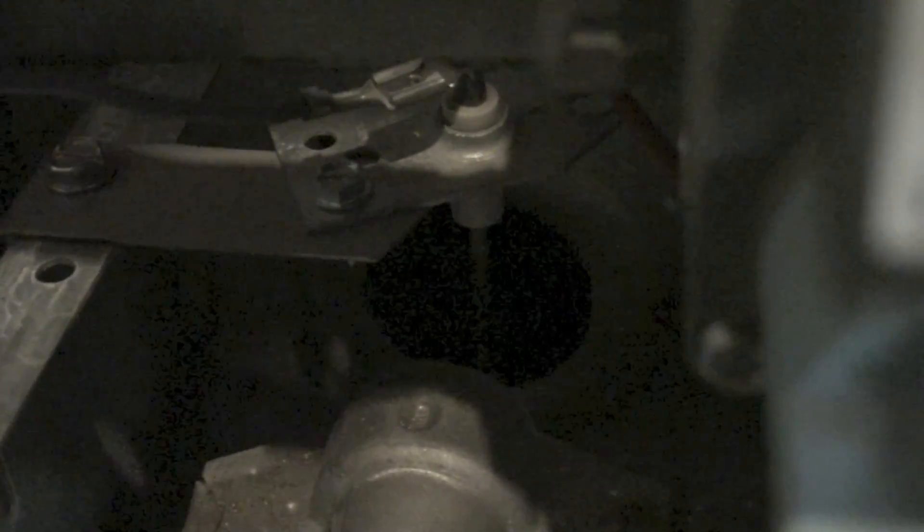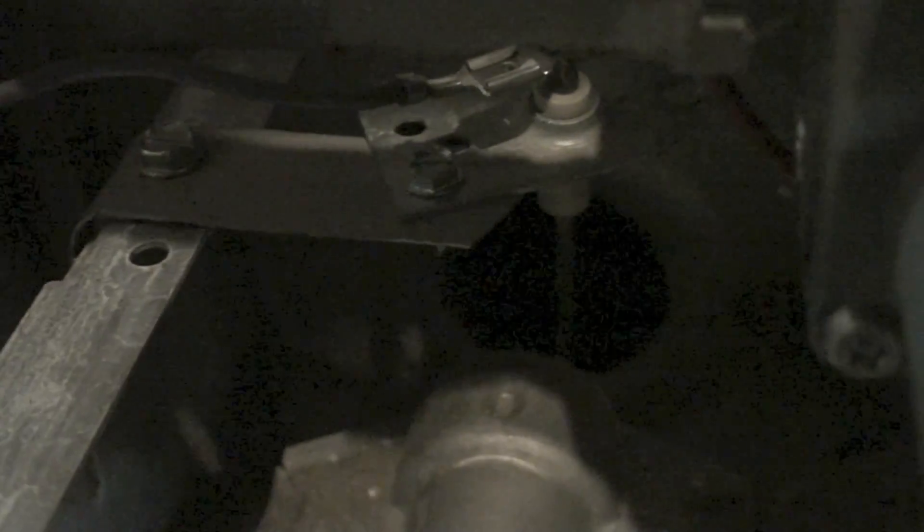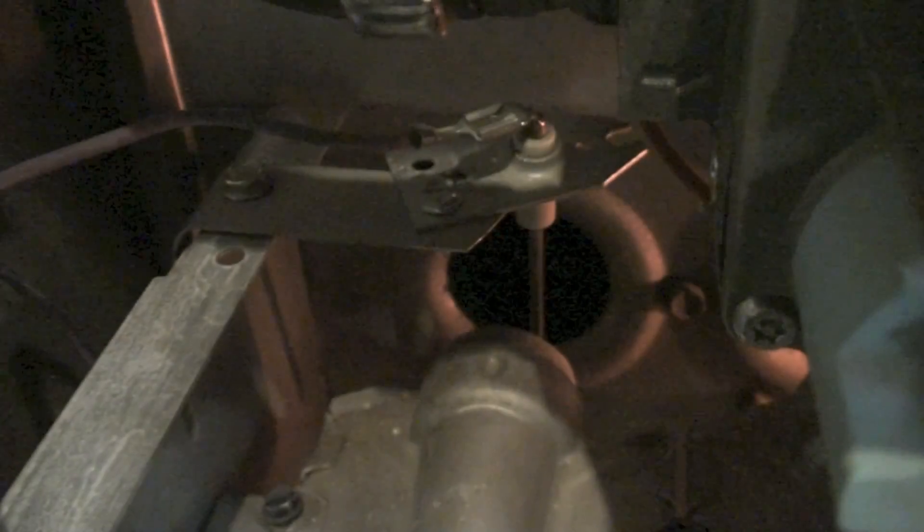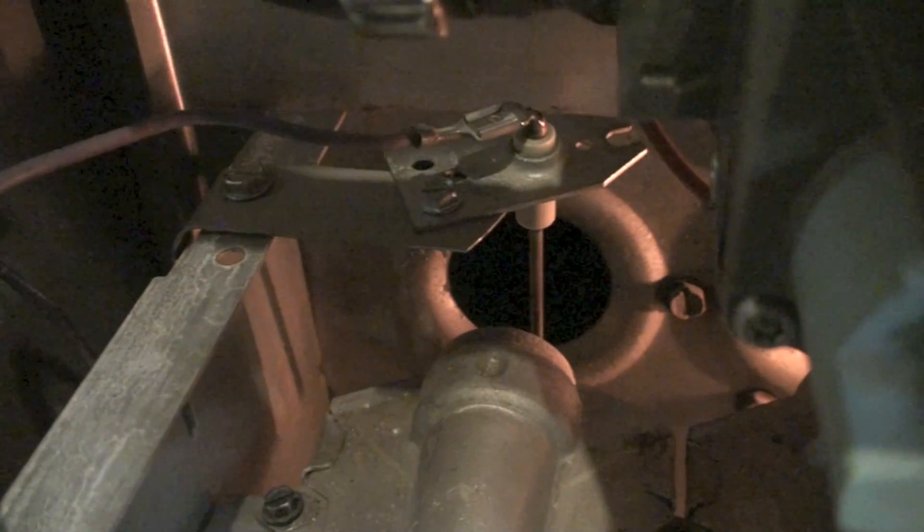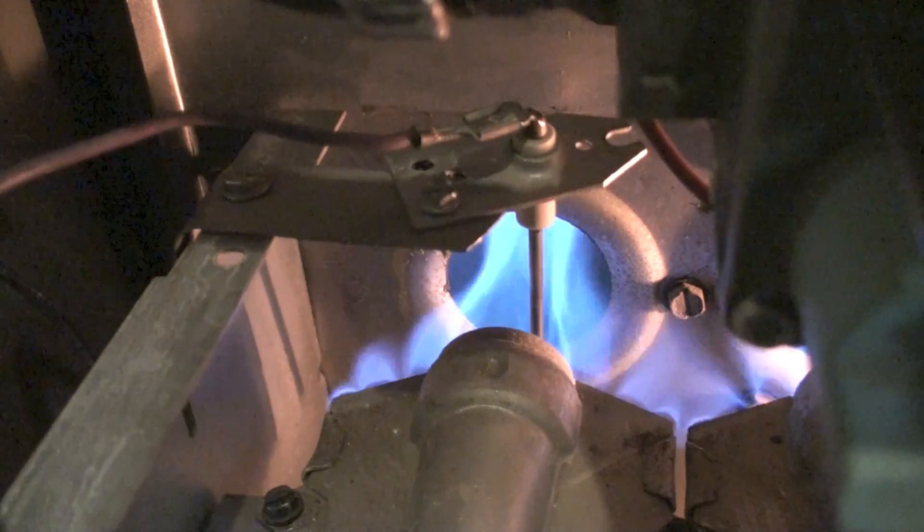And it works by flame rectification. Flame can actually transmit power. So if I feed an alternating current into the flame rod to the chassis or the burners, when it's negative going to the flame rod, power is passing from the flame rod to the burners.